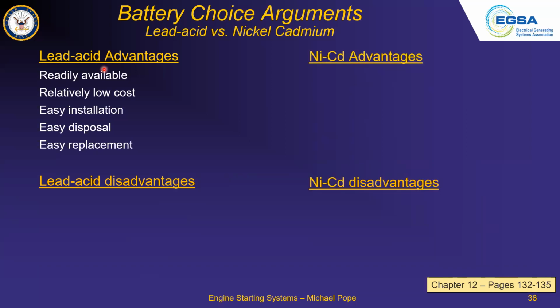What about disadvantages of the lead acid? Safety hazard from the acid, and hydrogen generated during charging. So you need ventilation for the room. That's important. You don't want to stick your head in there if there's any doubt of that in your enclosure if it's been discharging.